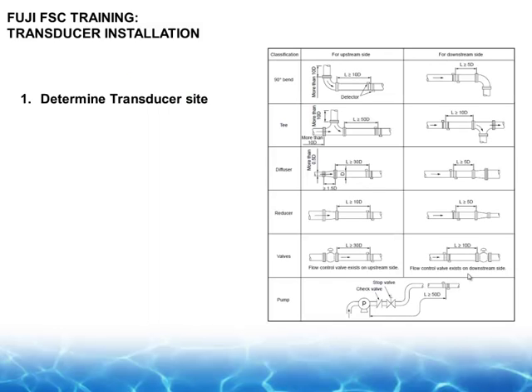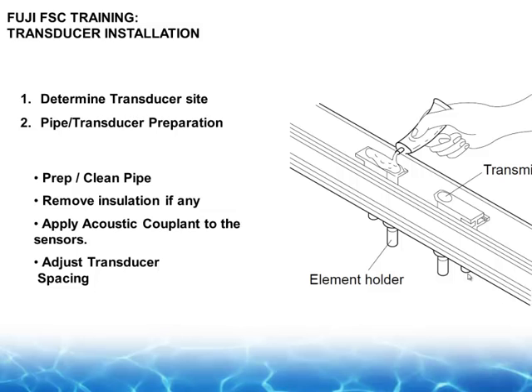So then we need to put the sensor on the pipe. As we said before, we need the traditional 10 to 15 pipe diameters, longer if you have a major obstruction. And we need to get the pipe ready to put the transducer on. If we have insulation, remove that from the pipe. Do not cut out little windows or little puzzles and put the sensors in there, because that never works. If you have insulation, make a horizontal cut, two complete circumferences, and peel it all back like a bed sheet off the bed. Then put your sensor on the pipe, and then you can put the insulation on top of that.